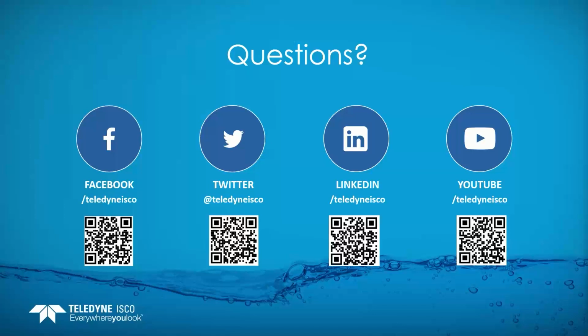First one I got is, can the AV sensor read level if it's covered with sediment? Yes, it will continue to read the level because it's a pressure transducer. Your levels may be elevated slightly because the sediment is actually displacing the water, but you will continue to read the level. Now the velocity you may struggle with because it isn't able to transmit the Doppler signal out because it's covered with sediment, but you could still get the level readings. And the nice thing about that is, as long as we got the level, you could use that to maybe calculate your flow with Manning's formula.